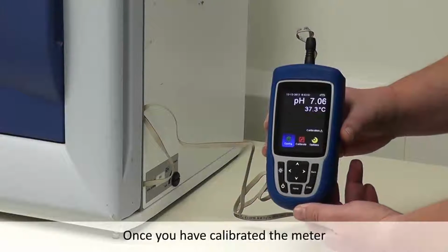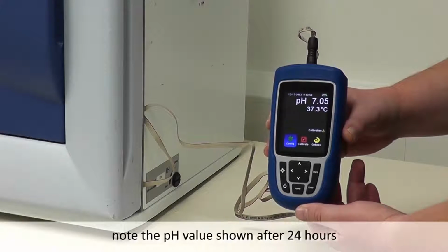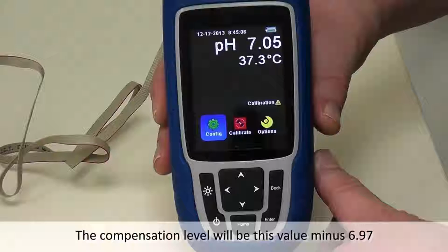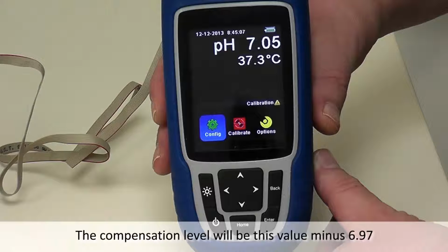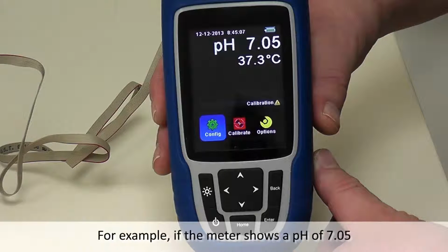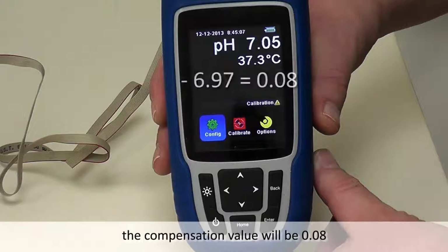Once you have calibrated the meter, note the pH value shown after 24 hours. The compensation level will be this value minus 6.97. For example, if the meter shows a pH of 7.05, the compensation value will be 0.08.